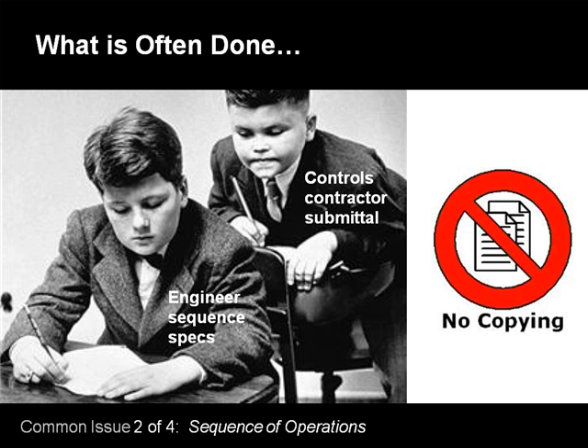The problem with that is the controls guy doesn't want to have his stuff rejected. So he gives you back a thing to reject your own work. You know, that's what he's trying to do. He doesn't want to put any more time than he has to into it. And the problem now becomes, how do I get the right sequence that's going to go into the field? Because here's what's going to happen. You approve that submittal, and then in the field, the controls contractor does exactly what he does on every other job that he's ever done. He's got a box full of controls programs that he's going to run.